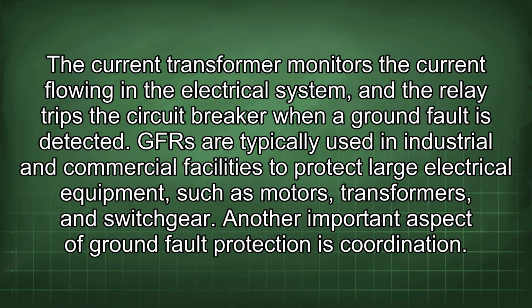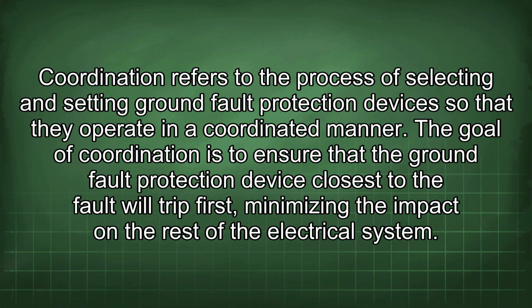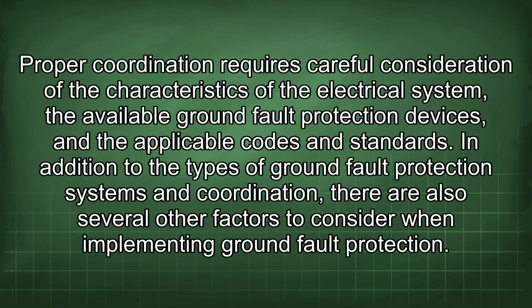Another important aspect of ground fault protection is coordination. Coordination refers to the process of selecting and setting ground fault protection devices so that they operate in a coordinated manner. The goal of coordination is to ensure that the ground fault protection device closest to the fault will trip first, minimizing the impact on the rest of the electrical system. Proper coordination requires careful consideration of the characteristics of the electrical system, the available ground fault protection devices, and the applicable codes and standards.